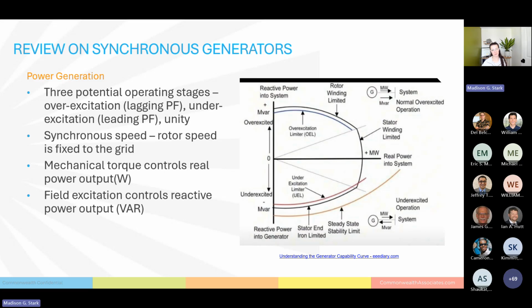And then this other condition that we talk about is underexcitation. And this is when the generator is pulling VARs from the grid. It's absorbing reactive power from the grid. And at this point, the generator terminal voltage is lower than the system voltage. So what you see when it's overexcited is generally the generator is trying to push VARs, it's trying to keep voltage up, keep voltage stable, and provide power. In underexcitation, you generally see that the generator is trying to bring voltage down. The system voltage is too high, and the generator is absorbing reactive power to bring system voltage down. And each of these introduces different strains and limitations on the generator that require protection and coordination via PRC 19.